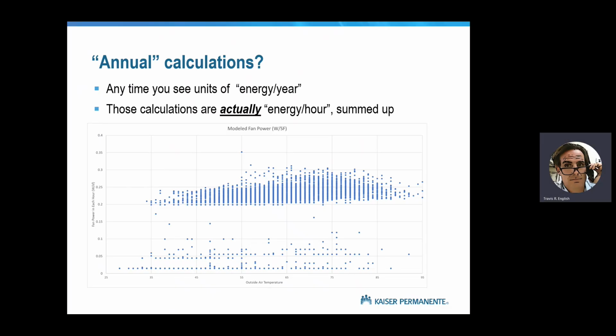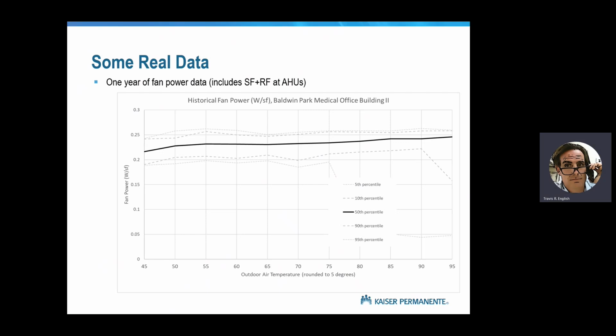By the way, if you opened this building tomorrow at noon and you looked at it at 1 p.m. and it was using 0.4 watts per square foot of fan power, you could fail the building immediately in the first hour, right? That's what we mean by you don't have to wait a year. Okay, so let's look at some real data. This is 1 year's worth of data, and it's for that building that you just saw the model for.